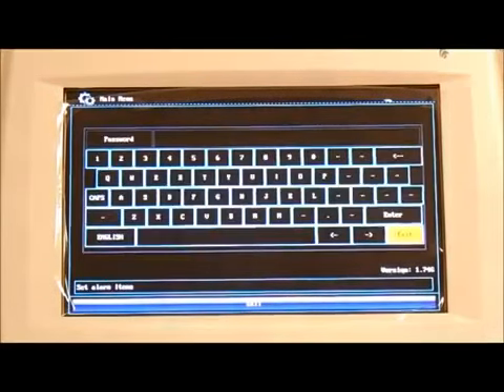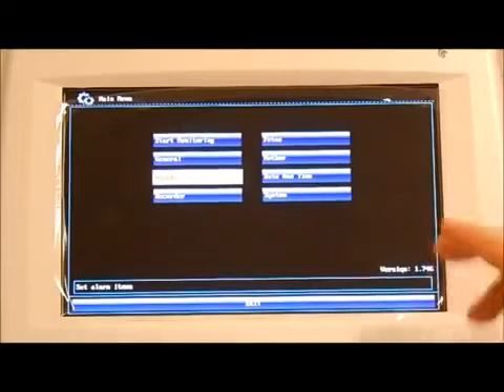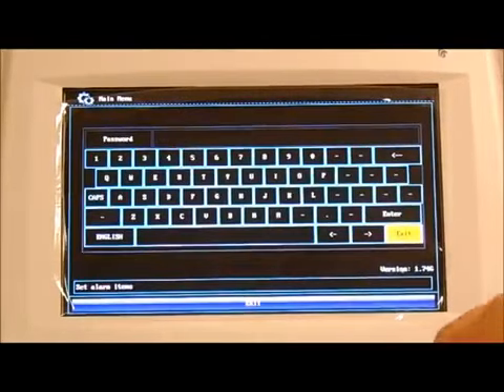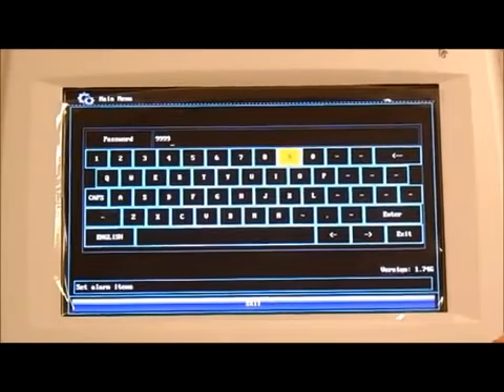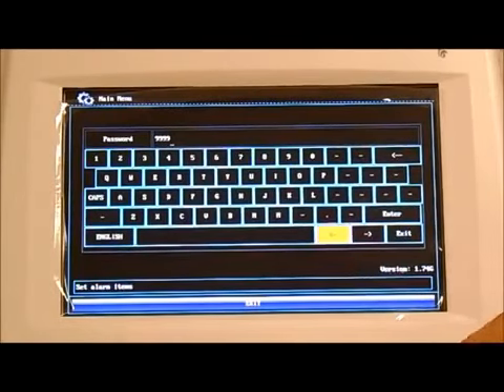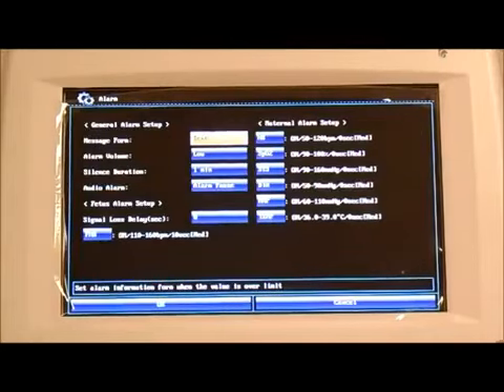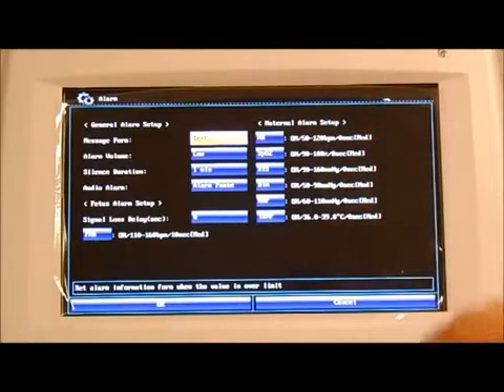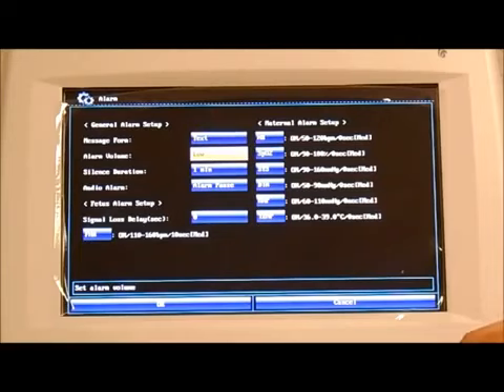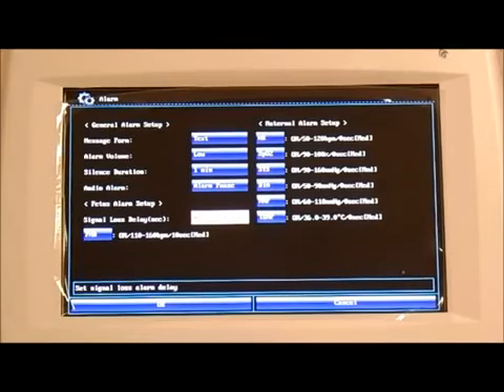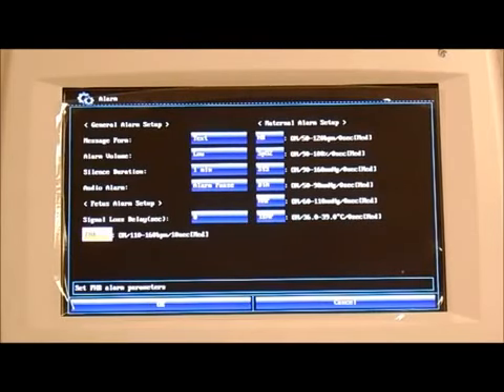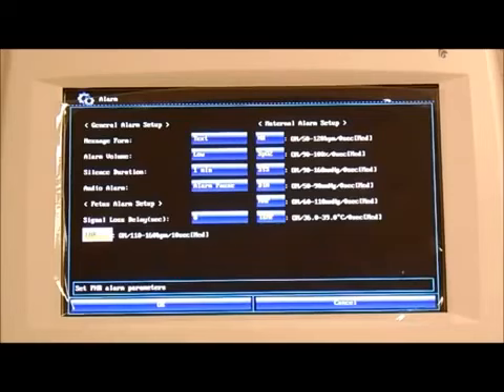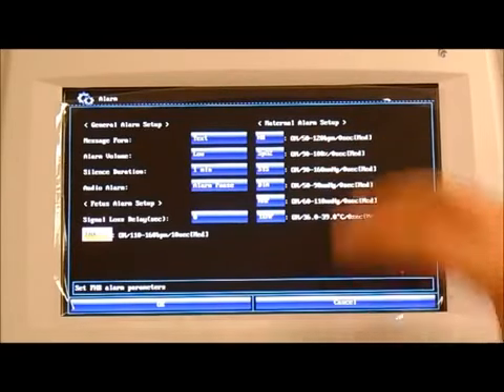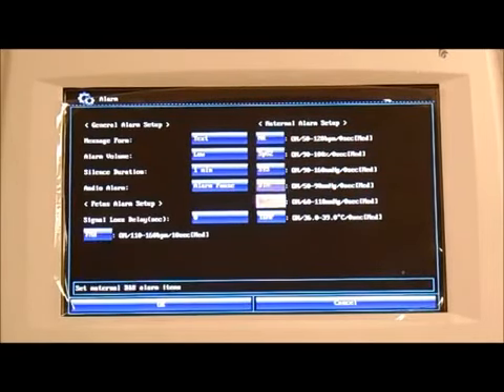The alarm, this is where we adjust the alarm settings. We press to select it, and the password is 999999. So it's 6 9s in total. You press enter, and now you can adjust the upper and the lower limits of all your parameters: your heart rate, your SpO2, and your fetal parameter alarms. By default, it'll have the standard alarms, which are found in every patient and fetal monitor, but you can always go in and modify them to your preferences.